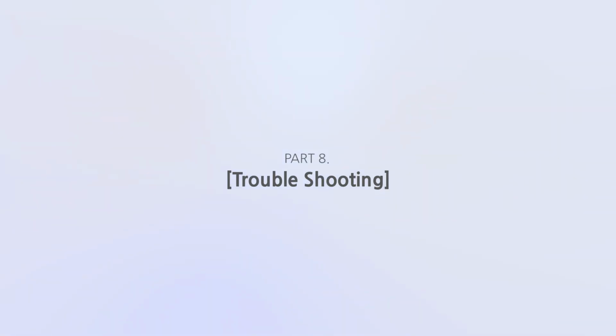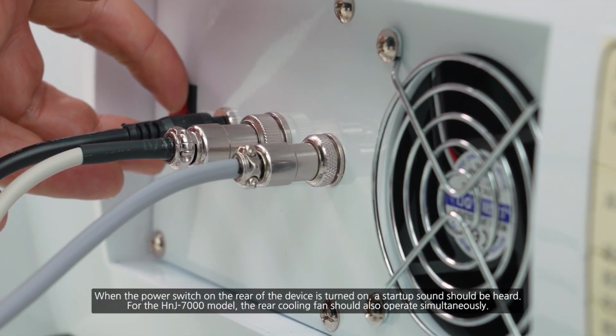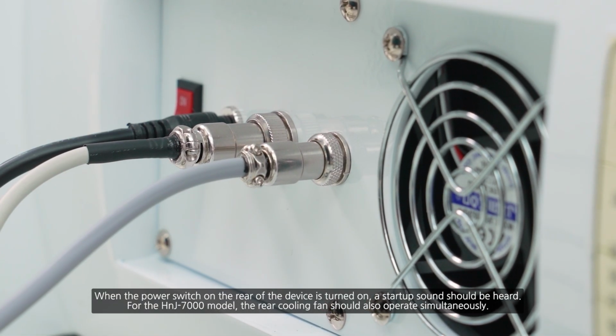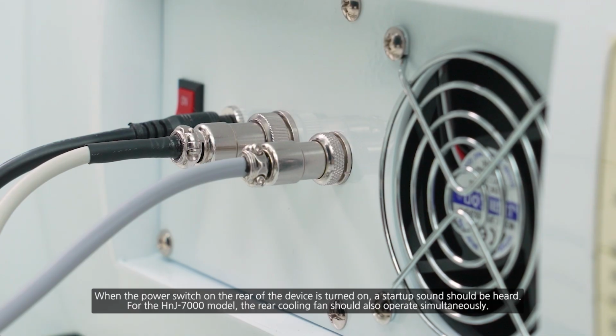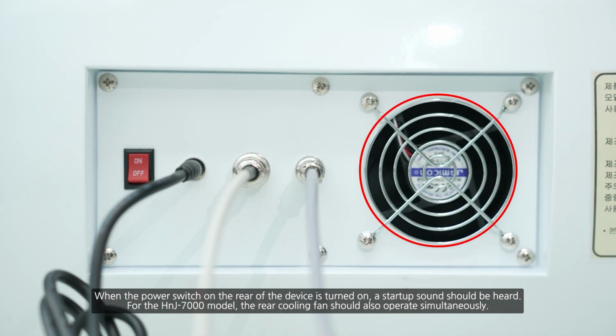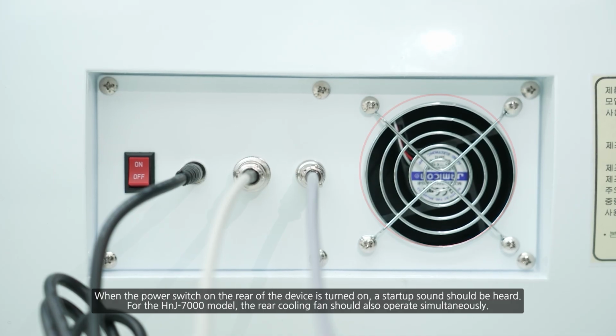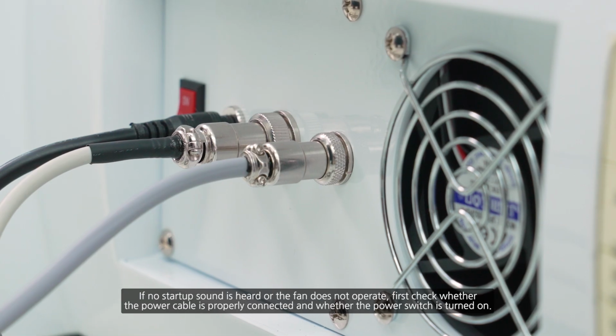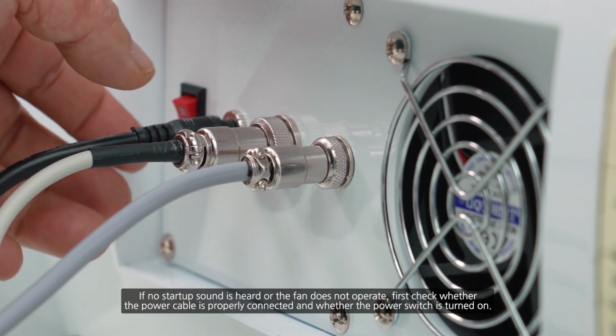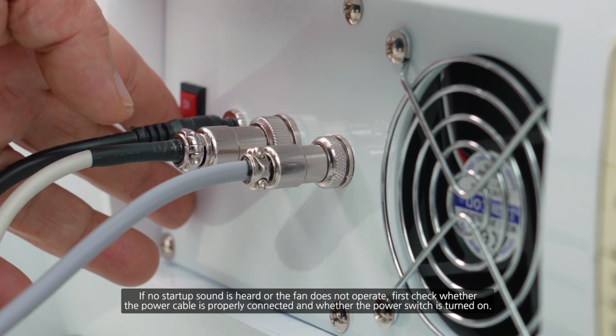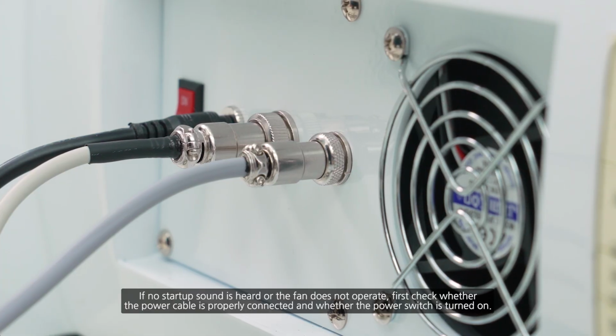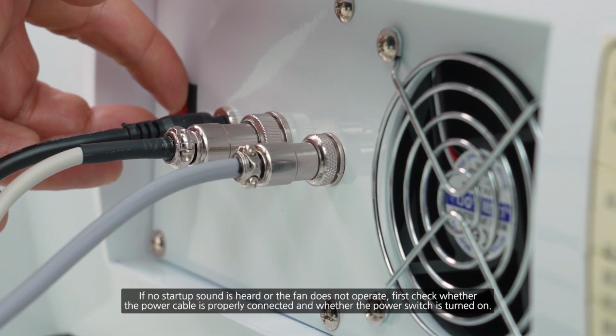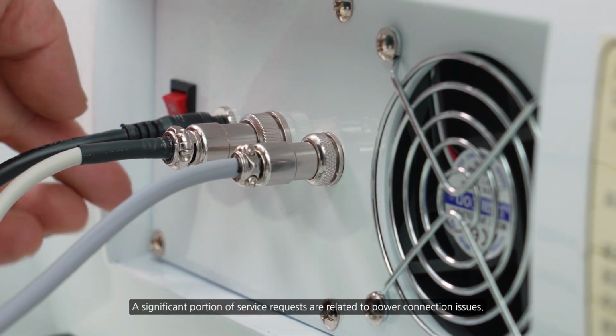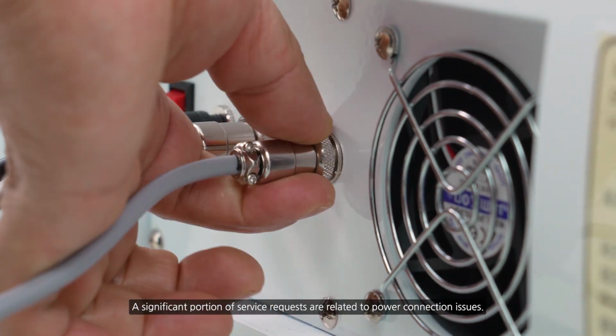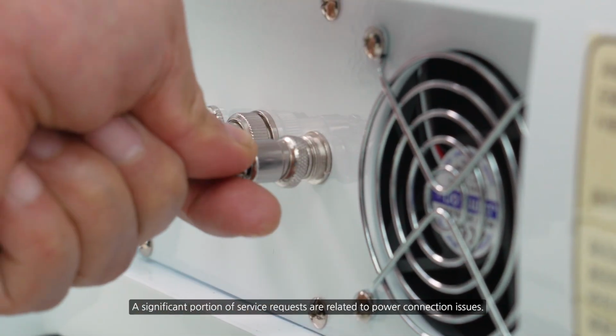Number 8. Troubleshooting. Number 8-1. Power malfunction. When the power switch on the rear of the device is turned on, a startup sound should be heard. For the HNJ 7000 model, the rear cooling fan should also operate simultaneously. If no startup sound is heard or the fan does not operate, first check whether the power cable is properly connected and whether the power switch is turned on. A significant portion of service requests are related to power connection issues.